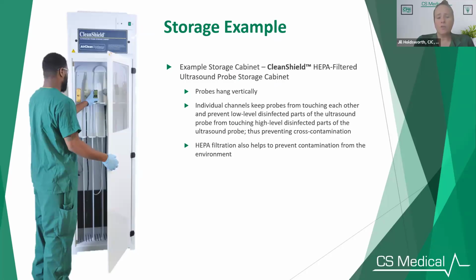So this is a great example of an appropriate storage example. It's made for probes because again, when you store these probes, they have to keep the low level disinfected and high level disinfected portions away from each other. They cannot touch. And they're made for a certain amount of probes. I have also seen people try to shove extra probes in there. So say it's a 6 probe cabinet, you can't store 8 probes in there because then things are going to be touching. So you do need to have probe cabinets made for probes and they need to be stored properly.